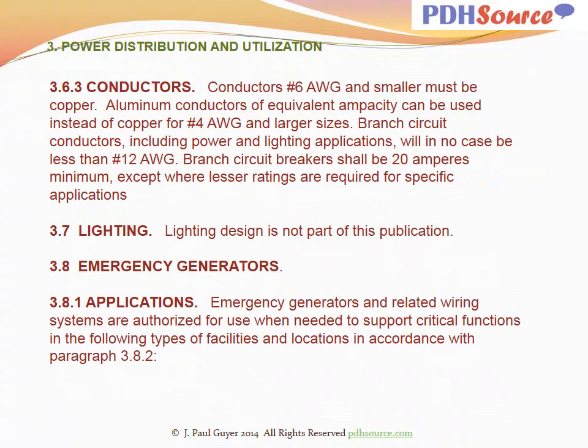With regard to conductors, conductors number 6 AWG and smaller must be copper. Aluminum conductors of equivalent ampacity can be used instead of copper for number 4 AWG and larger sizes. Branch circuit conductors, including power and lighting applications, will in no case be less than number 12 AWG. Branch circuit breakers shall be 20 amps minimum, except where lesser ratings are required for specific applications. Lighting design is not part of this discussion of interior electrical distribution.